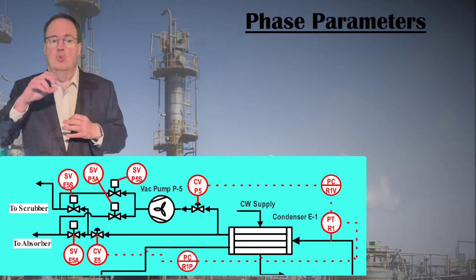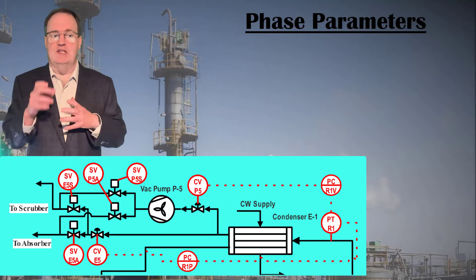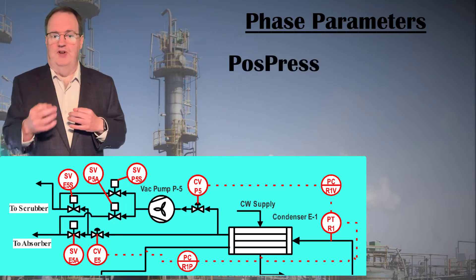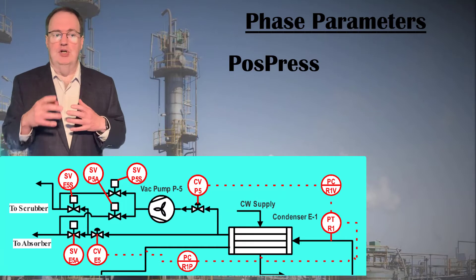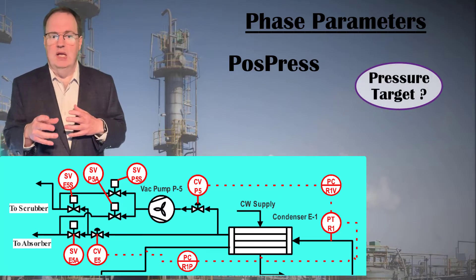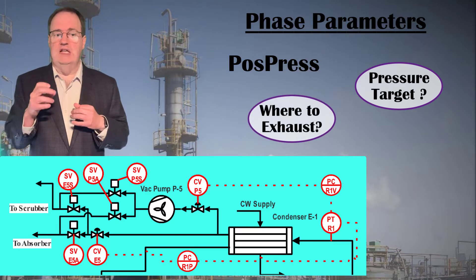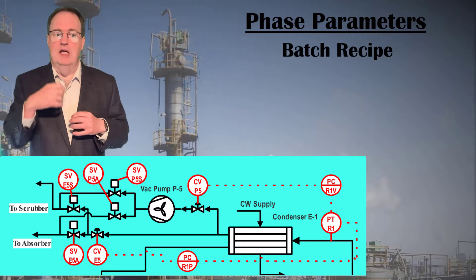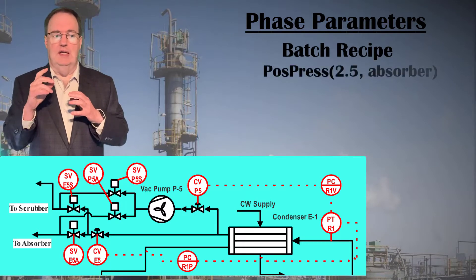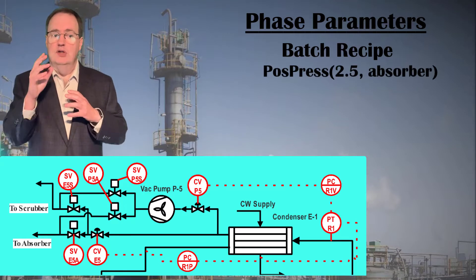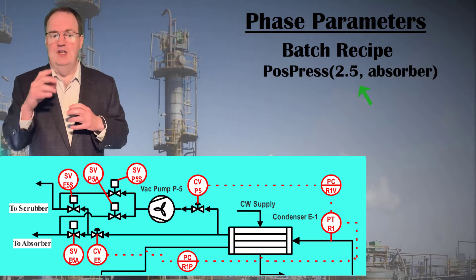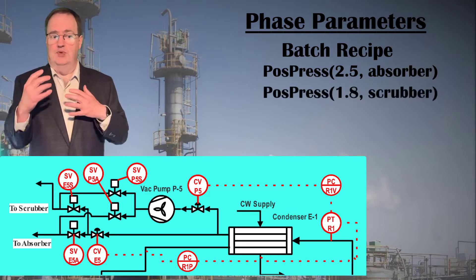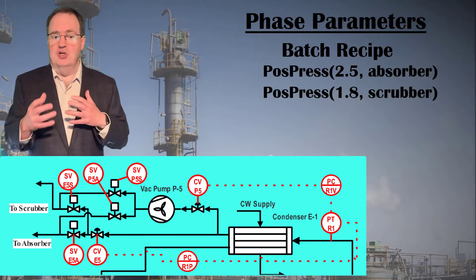Phases may have parameters, which are specific target numbers or instructions to the phase from the recipe that direct how to carry out the phase's task. If our positive pressure phase is called PosPress, it would need a parameter to tell it what pressure to target — let's say in bars — and another parameter instructing whether the vent discharge goes to an acid absorber or to a scrubber. So when used in the batch recipe, the phase name appears with values in brackets, like PosPress 2.5, absorber or PosPress 1.8, scrubber.